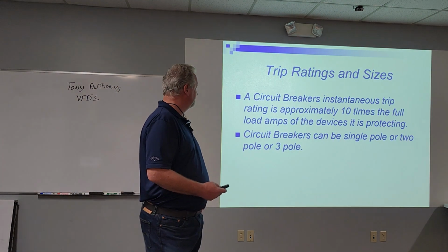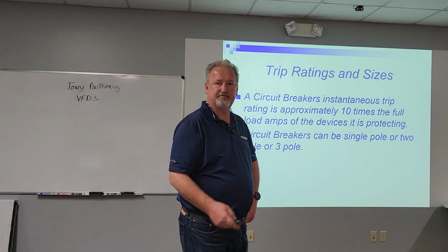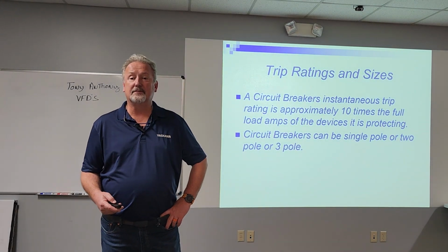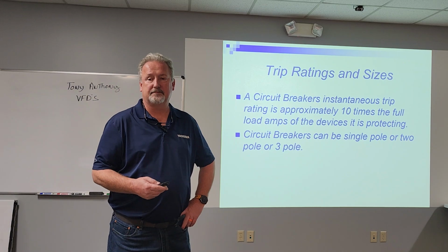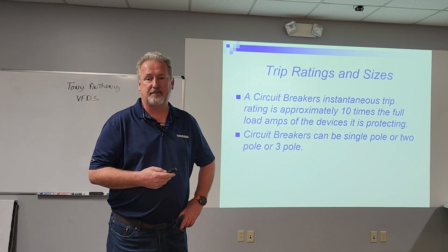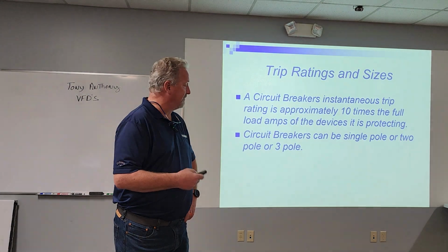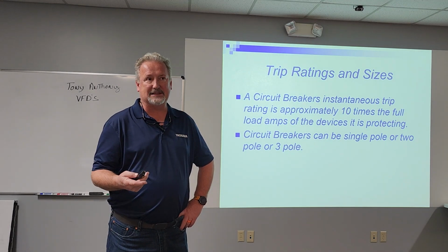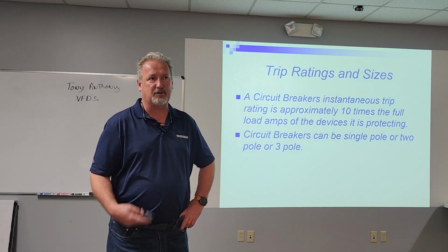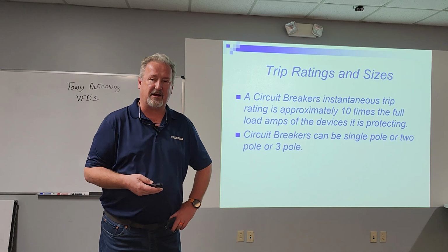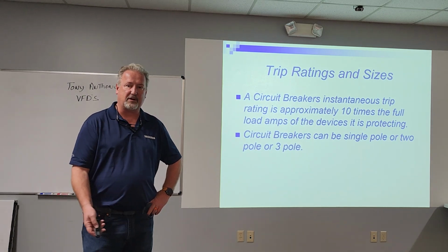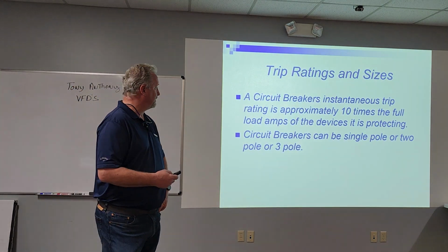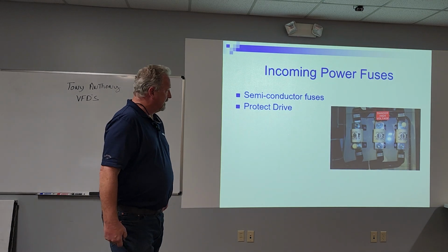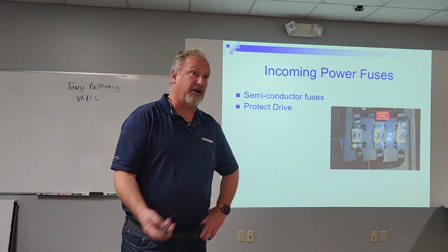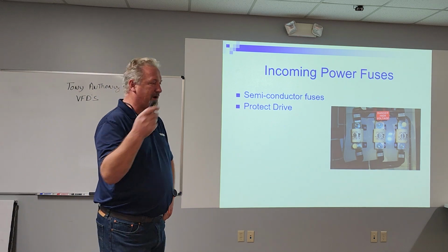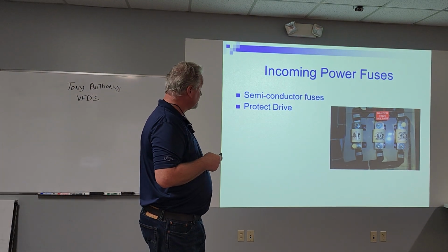And the interrupt rating on them too. The interrupt rating on them too, I would think would be another key. Yes. You want to make sure you have them set properly. I think NEC coding says a breaker feeding a drive has got to be 125 to 150% of the drive rating. And on larger drives now, they're requiring us, if we have a breaker, to put fuses back in them.